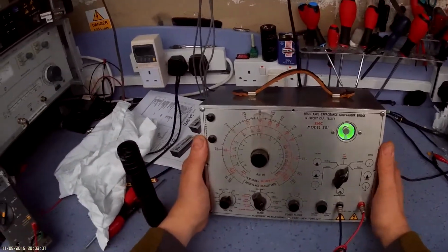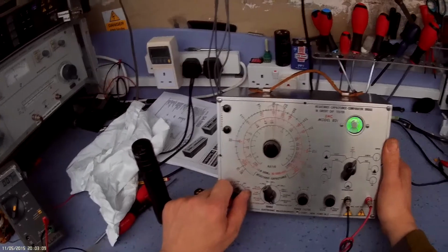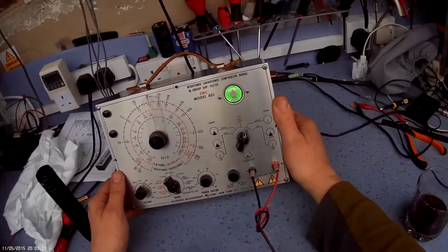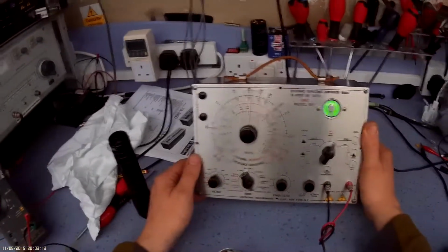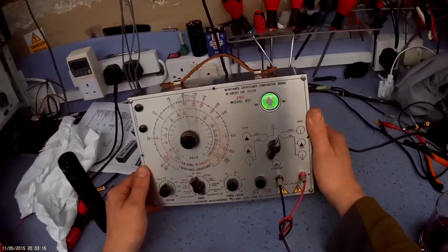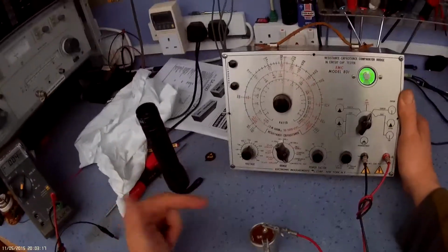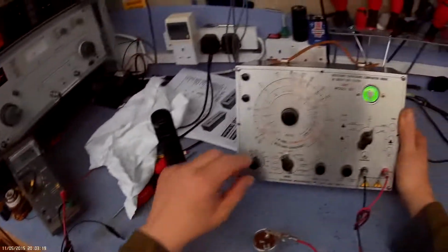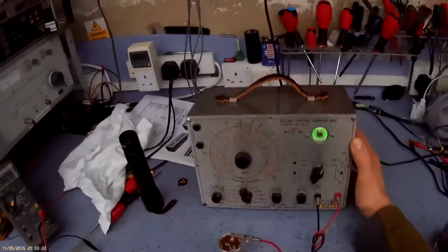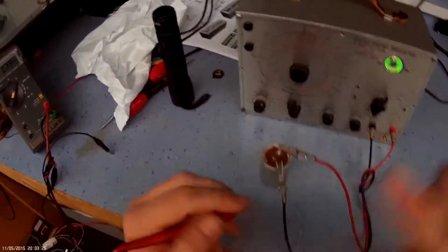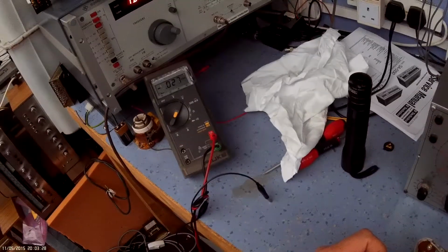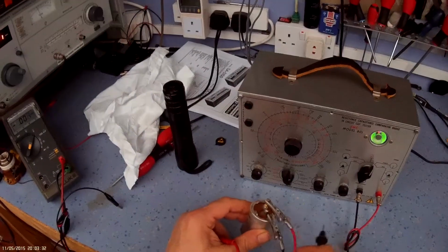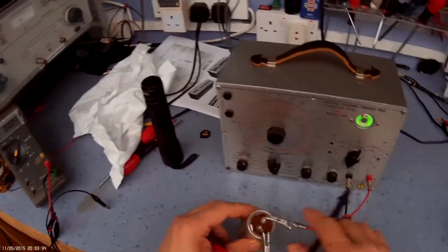But a useful test, if I reduce it to 250 volts, you see the eye opens initially and then closes. So certainly at around 200 volts, this capacitor is absolutely fine. Now you must be careful that when you finish with this test, you turn it to minimum, just to make sure the capacitor is discharged, and always check with the multimeter. There you go, you see it's dropped down, that it's okay, and just short it out to be absolutely sure.